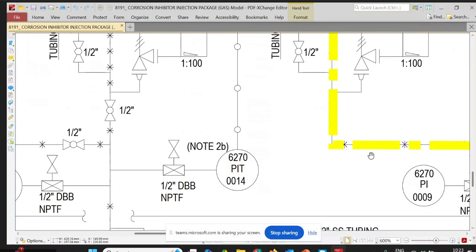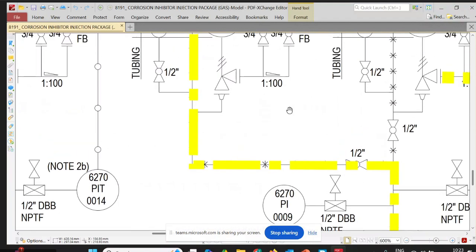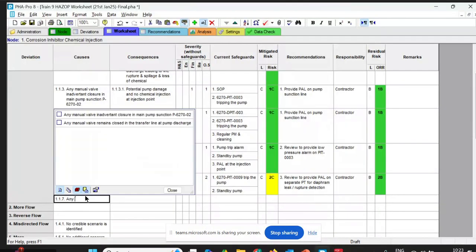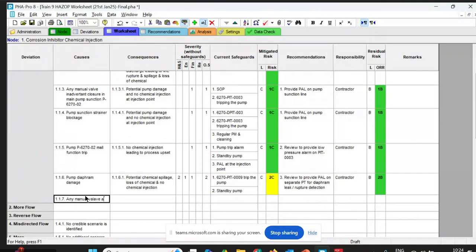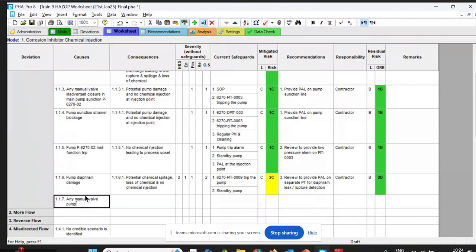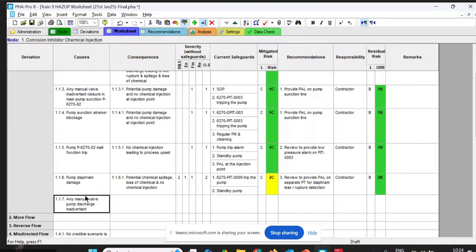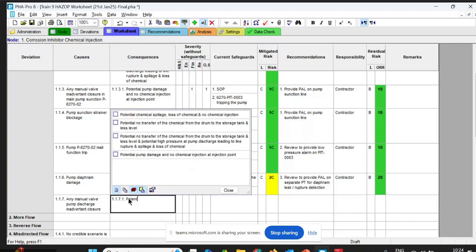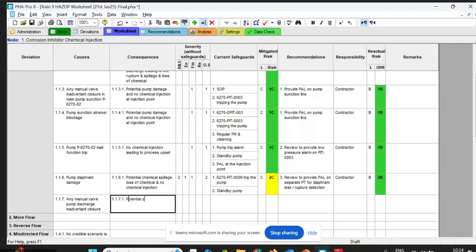Yes, very true. So now we are going to the pump discharge. At pump discharge, there is a manual valve. This can also have inadvertent closure. So this is high pressure, it will rupture. So I would say any manual valve at pump discharge, inadvertent closure. So potential high pressure, potential overpressure at pump discharge, leading to rupture.